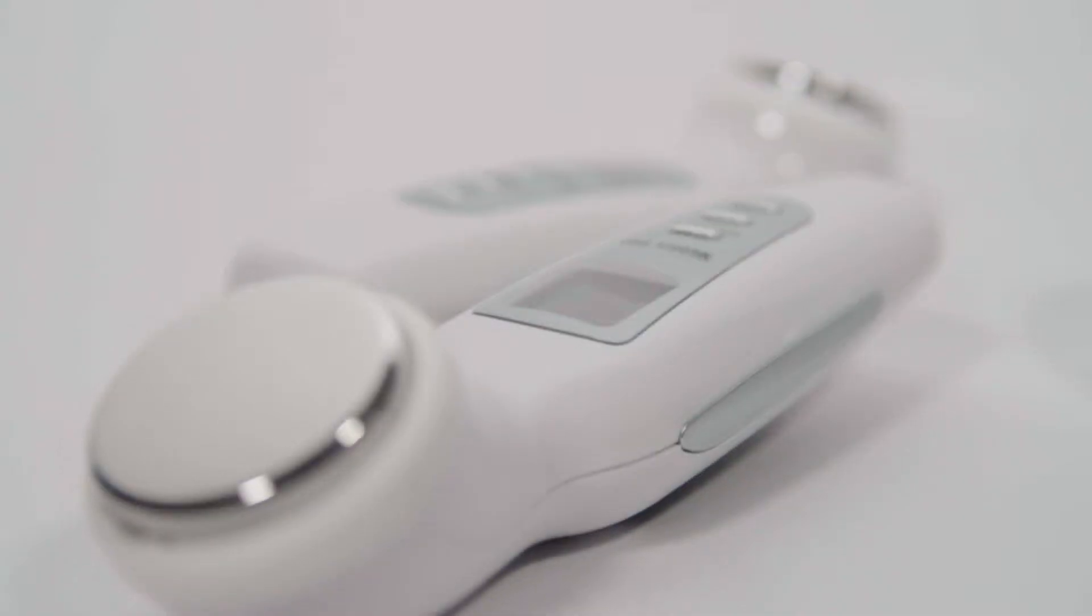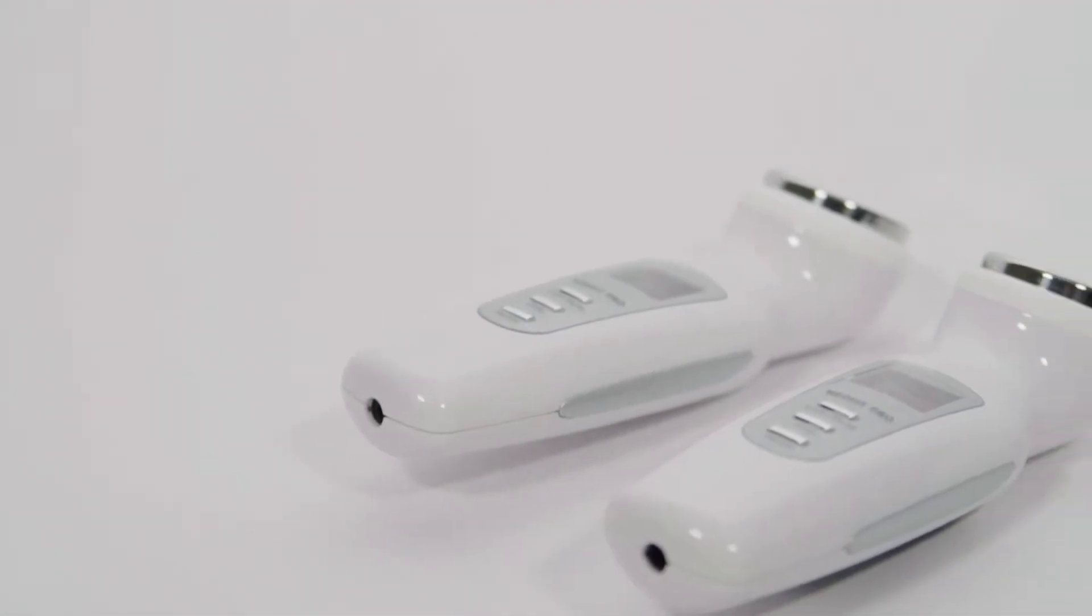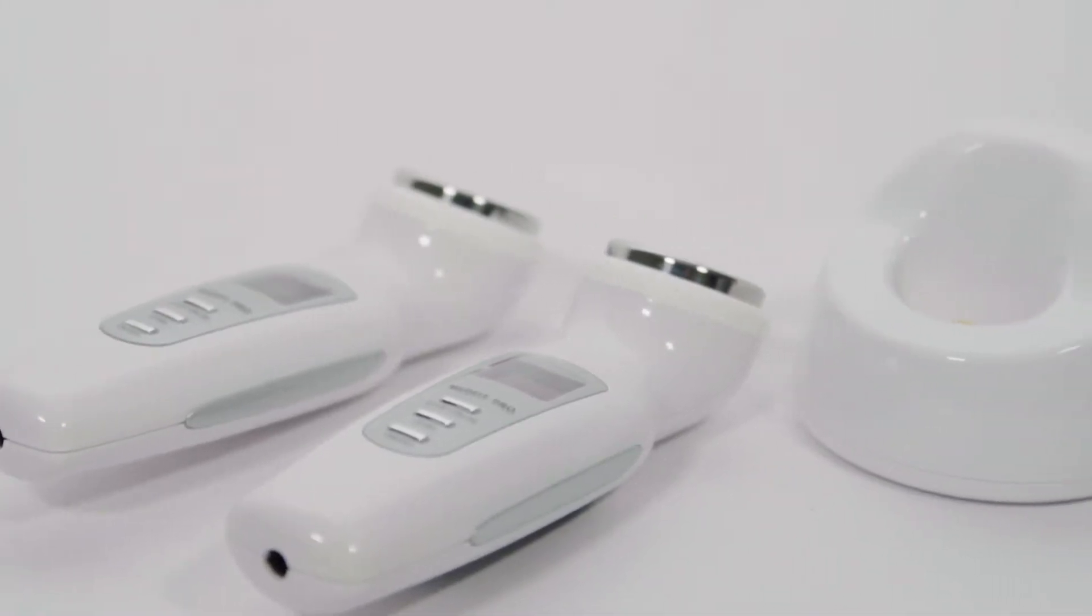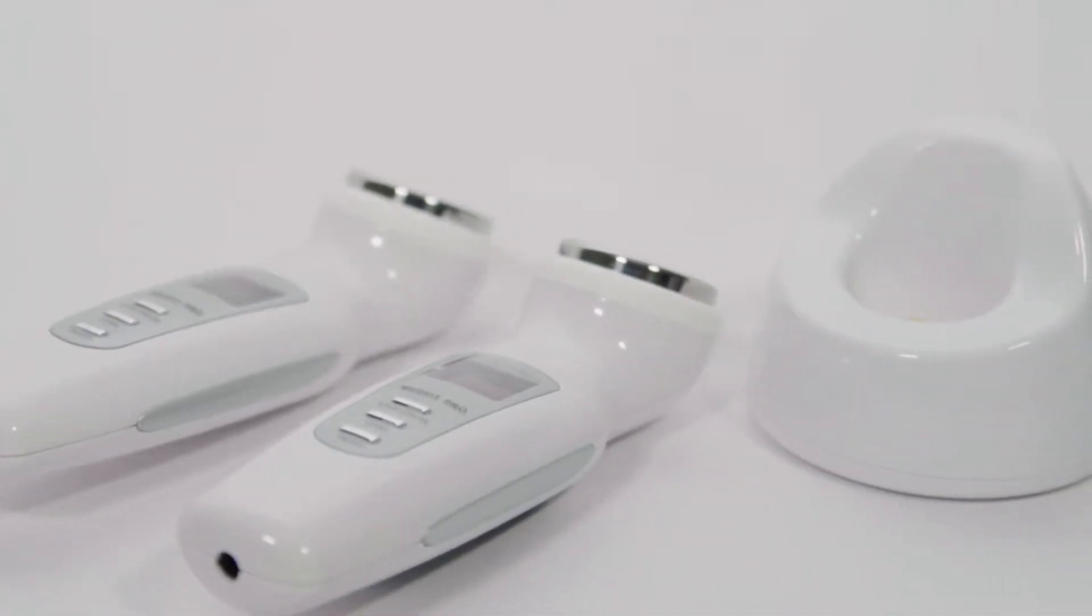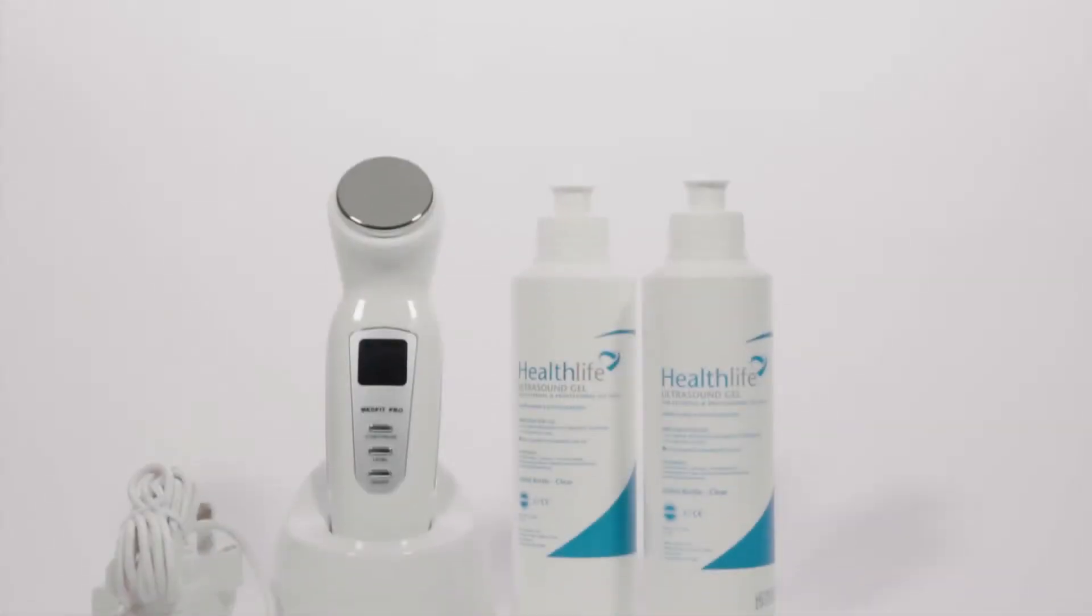The 1MHz has a maximum depth of penetration through muscle 7cm deep, whereas the 3MHz has far more superficial treatment depth with a maximum of 2.5cm.